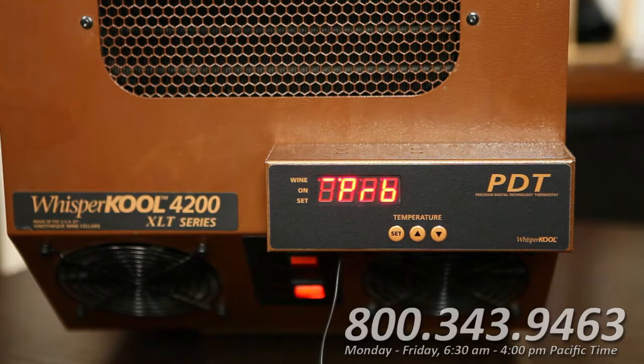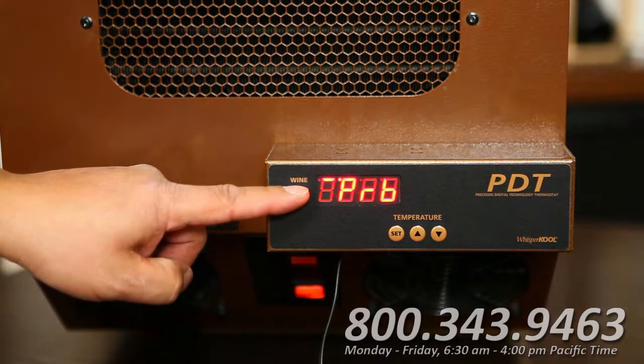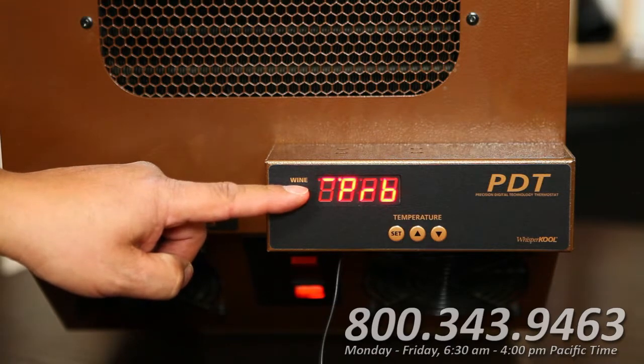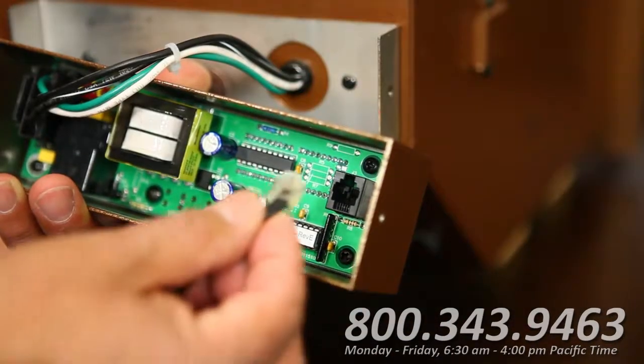Also, check your thermostat for error codes. For instance, if you see a PRB code, this means that the liquid temperature probe is not properly connected. To fix this, remove the thermostat and make sure that the plug is secure in the socket.